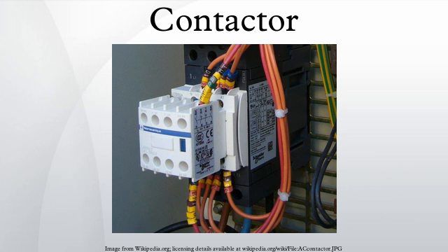Magnetic blowouts use blowout coils to lengthen and move the electric arc. These are especially useful in DC power circuits. AC arcs have periods of low current, during which the arc can be extinguished with relative ease, but DC arcs have continuous high current, so blowing them out requires the arc to be stretched further than an AC arc of the same current. The magnetic blowouts in the pictured Albright contactor more than double the current it can break, increasing it from 600 A to 1500 A.